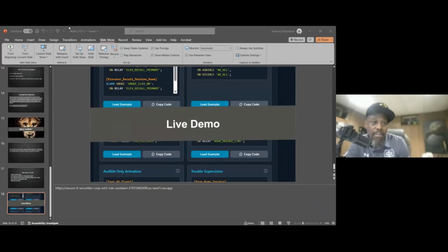And you also will have to define that in the rules when it comes to that central station, that CMS central station message. So if you're defining your rules for whatever the zone, let's say zone type pull, it wouldn't be contact, it wouldn't be these numbers for contact ID. For zone, it was only going to send 2 numbers, and it's a different way. You would just have to put the zone number. So if it's zone, whatever the zone is for pull, I don't know what it is, you would just put that in between these quotation marks for the activation and restore.